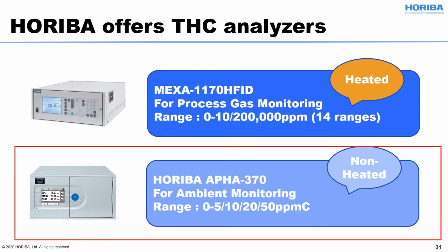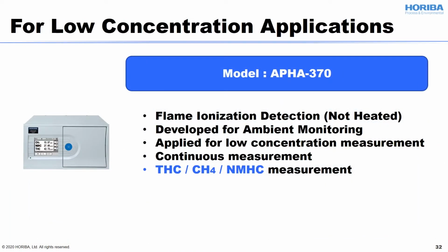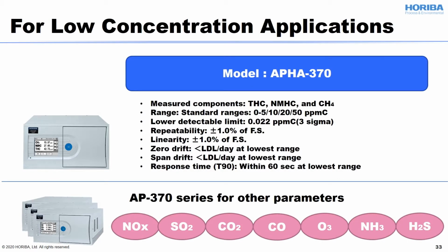Okay, now I would like to focus on the low concentration analyzer, APHA-370, which is a non-heated type of analyzer. This APHA-370 uses the same measurement method, flame ionization detection. APHA-370 was developed for ambient monitoring. It is applied for low concentration monitoring. It can be used for continuous measurement as well. APHA-370 can measure total hydrocarbons and methane and non-methane hydrocarbons. The range setting is from 5 to 50 ppmC. As you can see, APHA-370 can go to very low concentration, and the lower detectable limit is 0.022 ppmC. Linearity and repeatability is good, max 1% of full scale.